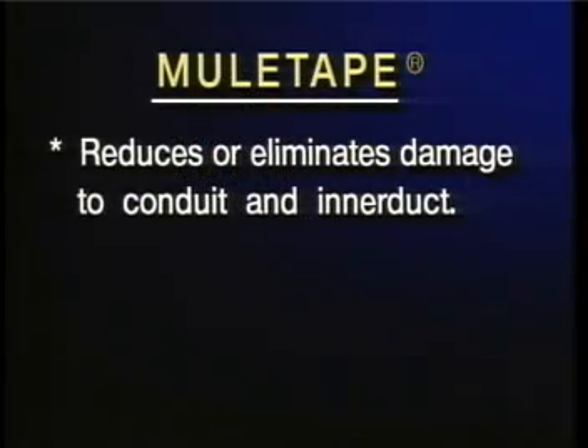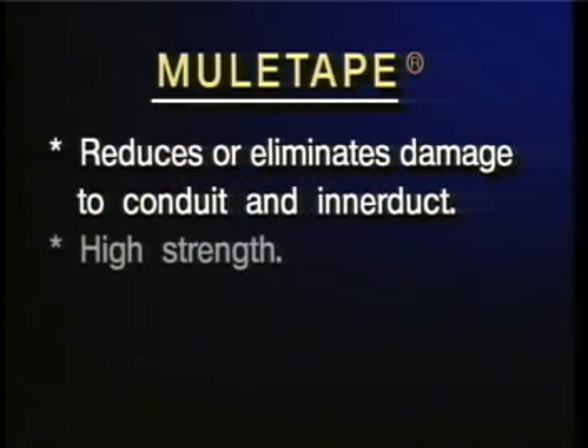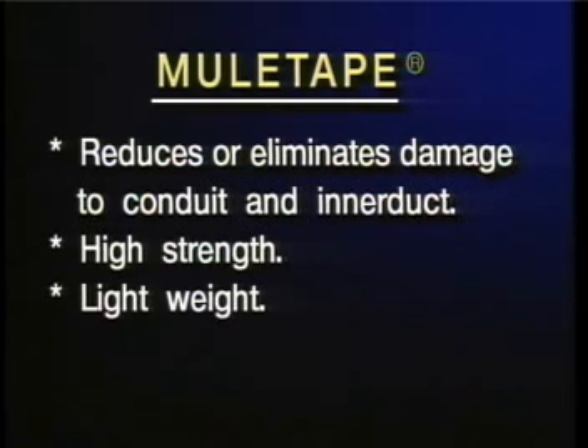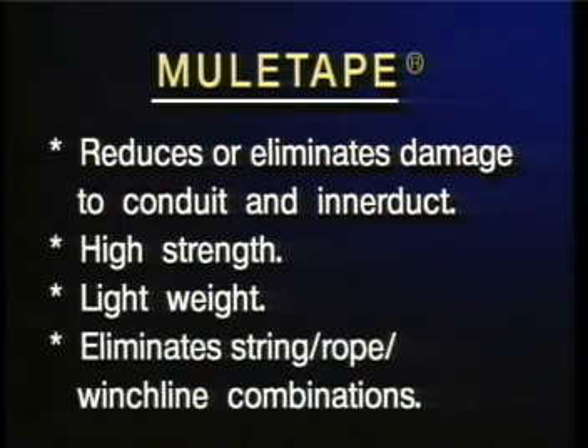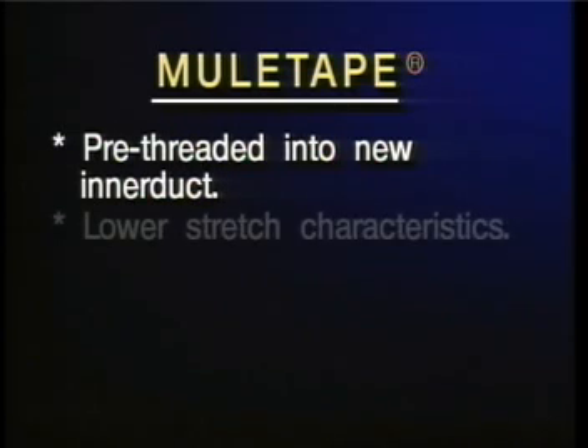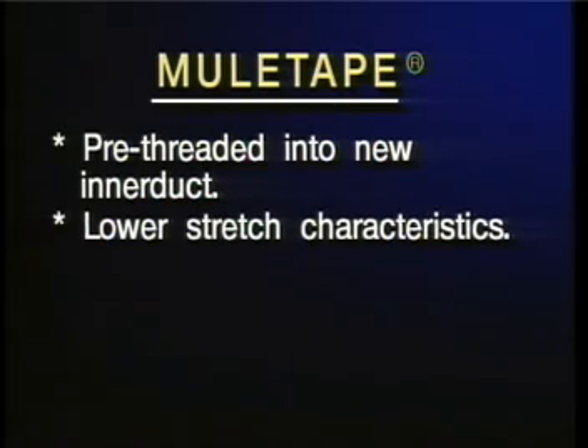Muletape not only greatly reduces or eliminates damage to conduit and innerduct, it also has many other cost-saving features. Because of its high strength and low weight, it can be blown directly into the conduit, eliminating the need for string, rope, winch line combinations. It can also be pre-threaded into new innerduct. Muletape has drastically lower stretch characteristics than standard polyrope, so it's less prone to crush capstans or cause injury due to snapback should a break occur.